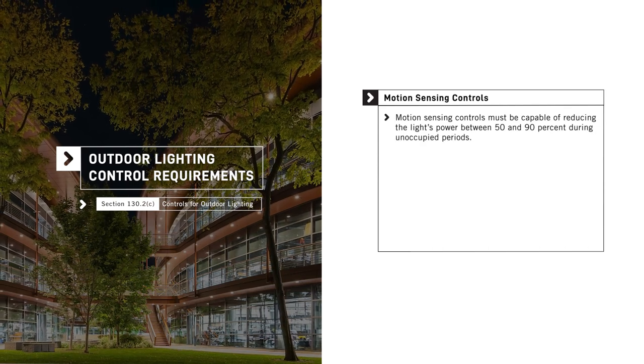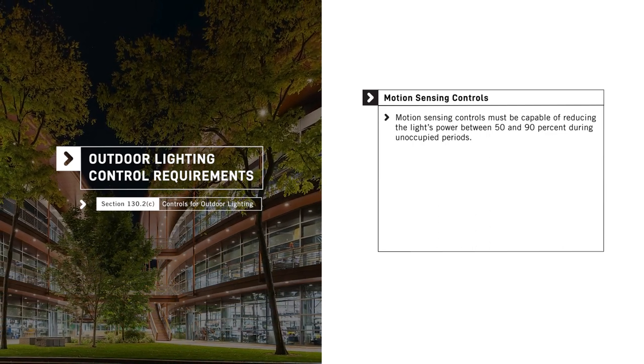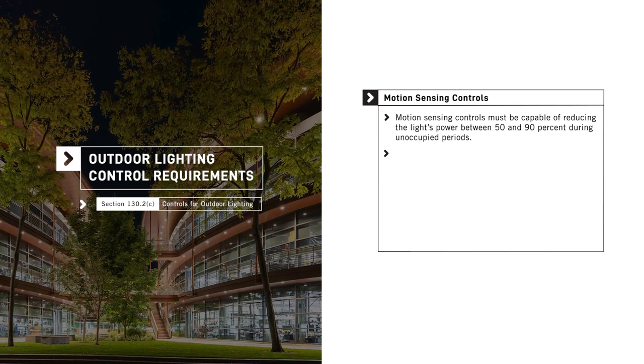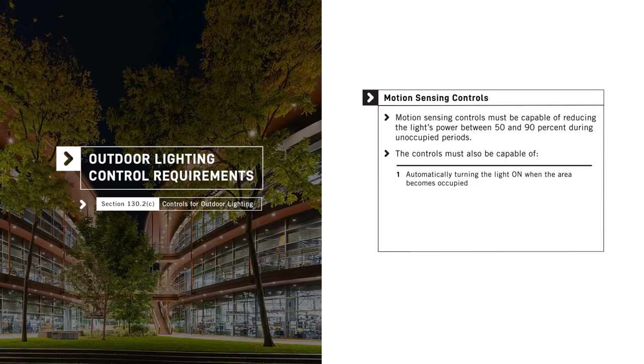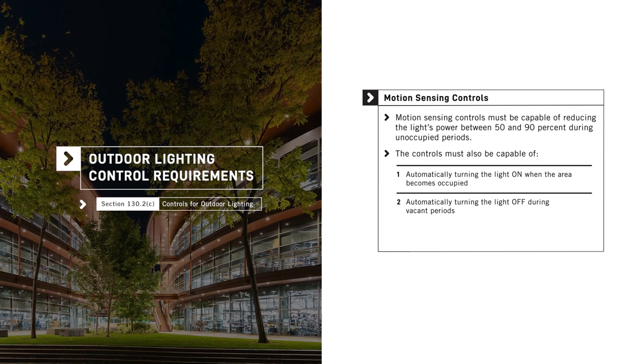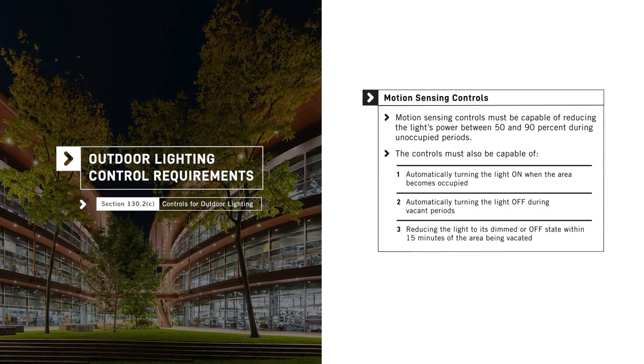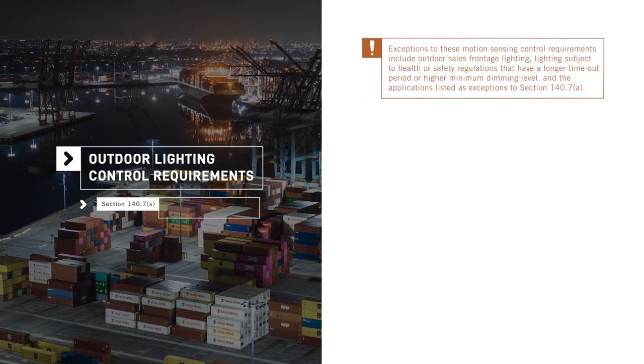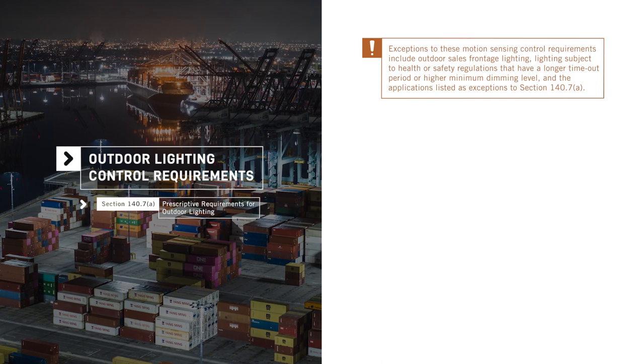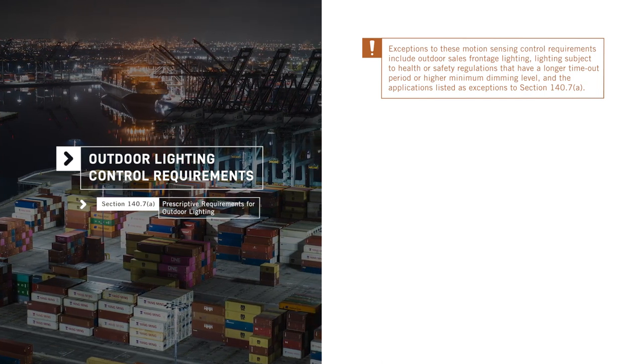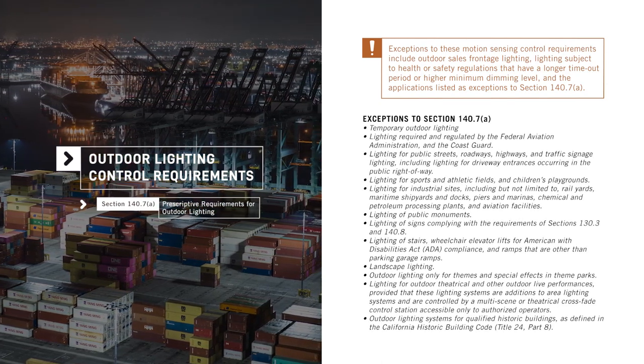Motion sensing controls must be capable of reducing the light's power between 50 and 90 percent during unoccupied periods, including those that occur during business hours. The motion sensing controls must also be capable of automatically turning the light on when the area becomes occupied, automatically turning the light off during vacant periods, and reducing the light to its dimmed or off state within 15 minutes of the area being vacated. Exceptions include outdoor sales frontage lighting, lighting subject to health or safety regulations that have a longer time-out period or higher minimum dimming level, as well as the applications listed as exceptions to Section 140.7.